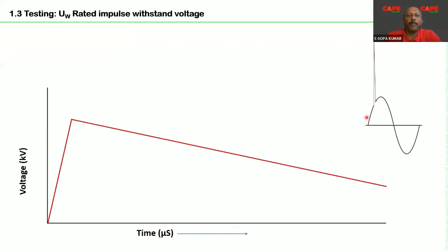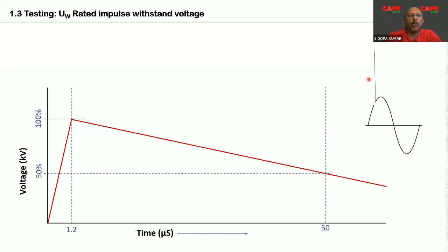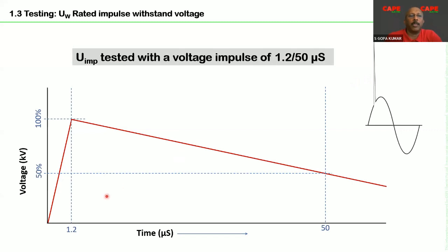You have here a sine wave, and there is a transient over voltage, let us say, which is created due to a surge, maybe a lightning or some kind of switching action. Now, the standard wave shape which is recommended in the standard for voltage impulse withstanding capacity is called 1.2 to 50 microseconds. It means this voltage is generated in a laboratory in order to test the short time insulation withstand of an equipment as a voltage waveform.